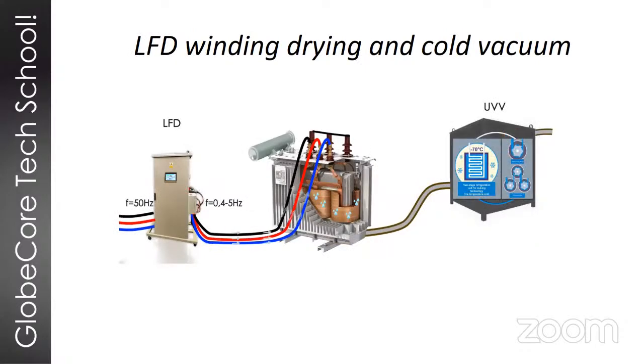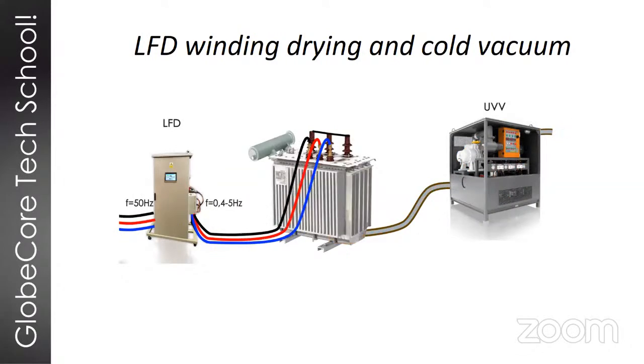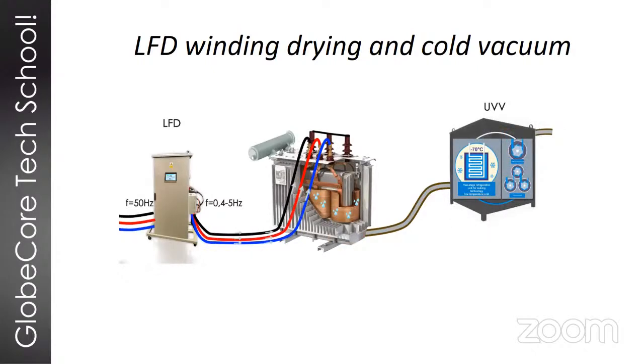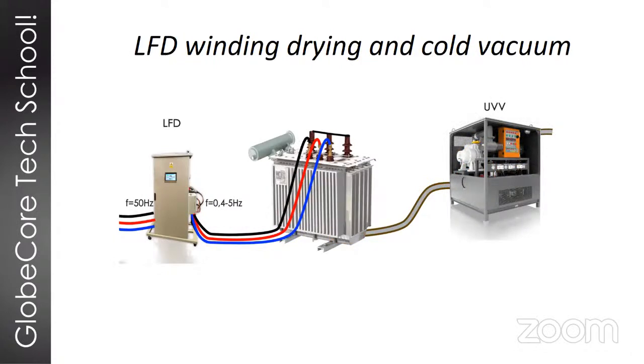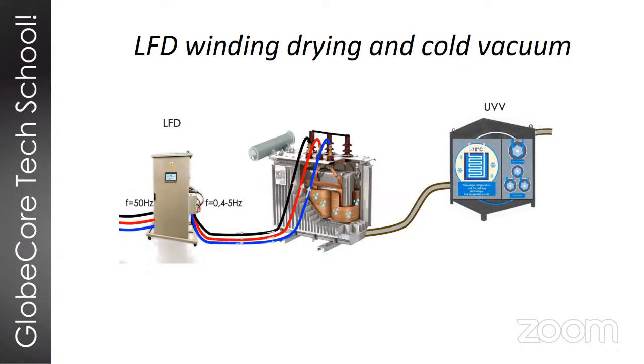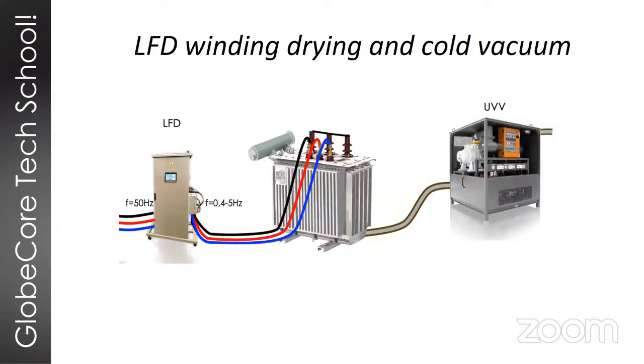All right, here we have a cold vacuum combined with an LFD system. So first off, the windings are heated by the LFD. Moisture evaporates into the transformer tank. And then basically what happens is that moisture is captured by the cold trap. It freezes in the cold trap, which has a temperature of -70 Celsius. And it's quite an efficient process, because it allows you to control the amount of moisture that is extracted from the solid insulation. However, this method requires that the transformer tank can withstand vacuum. If it cannot, then it's possible to use a special airtight bag into which the core is placed for this process. Right, next slide, please.